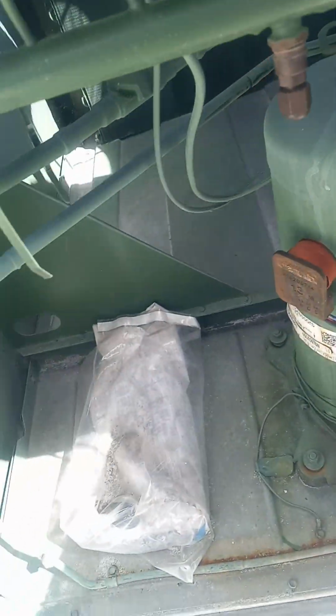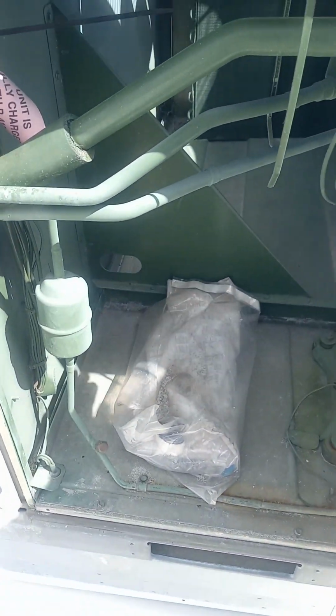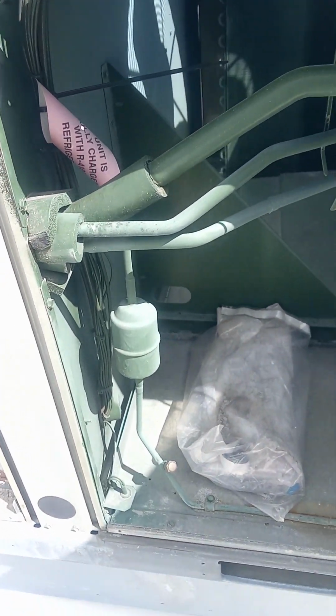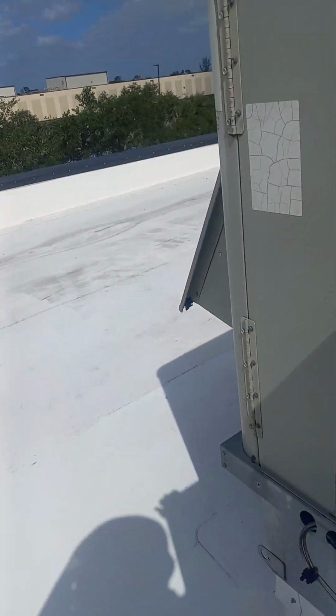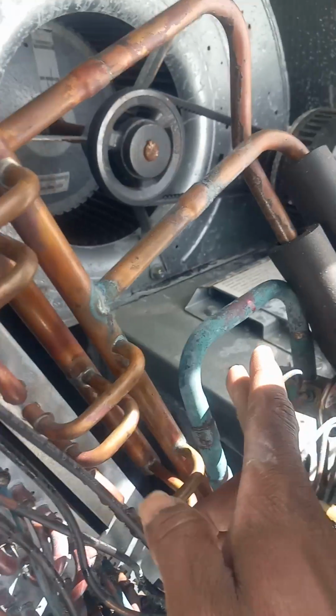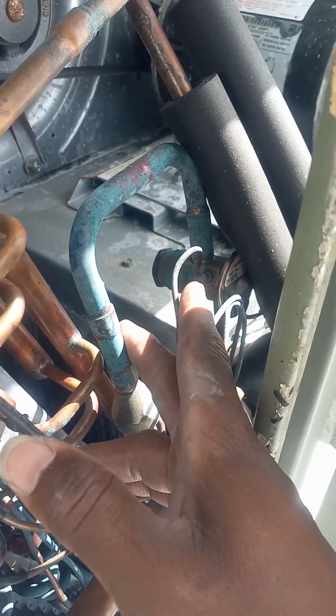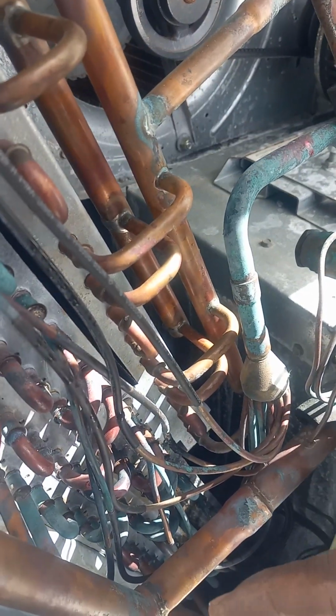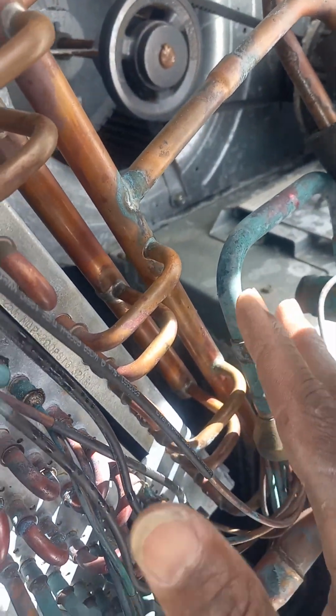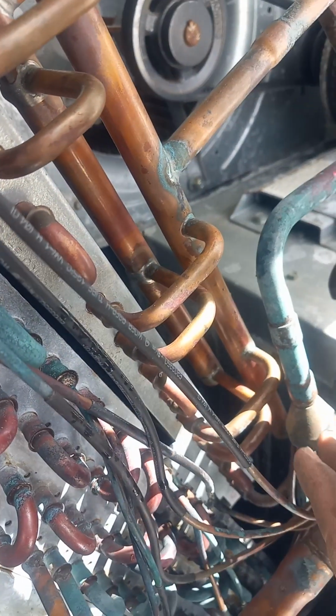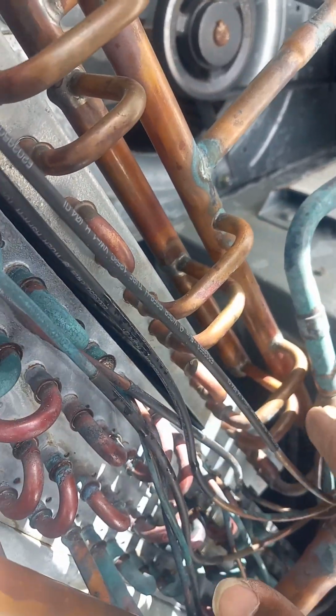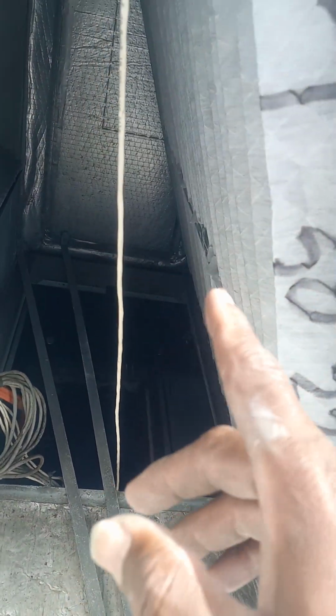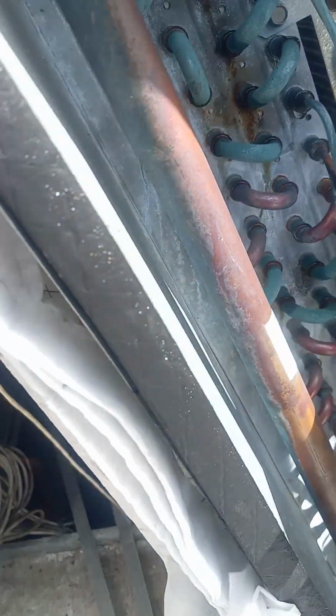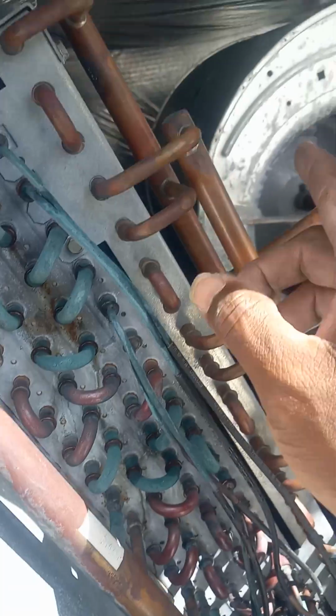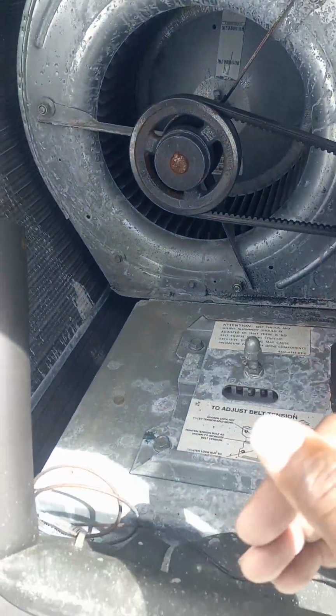The compressor pumps the gas from here, and it goes to the condenser. It condenses. It goes to the TXV, the TXV on the inside. This is the TXV right here. The TXV flashes that liquid and makes the components inside, like the bubbles and everything, expand. When it expands here, it starts flashing and sends a small amount of vapor and liquid mixture down here. By the time this liquid goes through the coil, when the fan spins, it pulls the air from the inside. That's the return. It pulls the air from the inside, sending the heat across that coil and boiling that refrigerant. When it boils the refrigerant, it gets cold. That air is then pulled from that and pushed into the building, and that's how you cool the space.